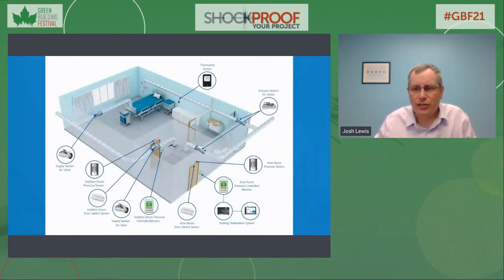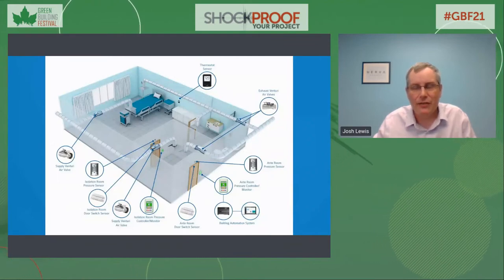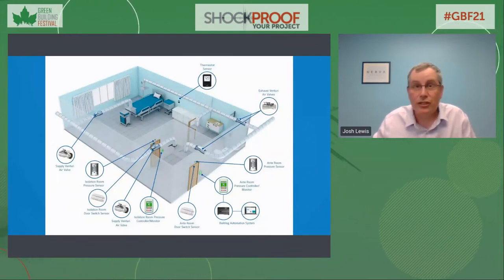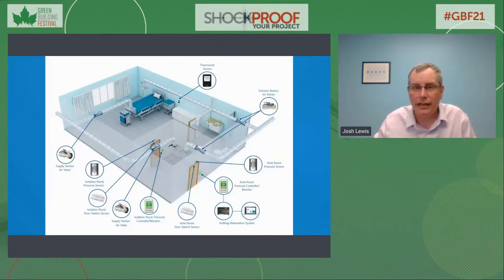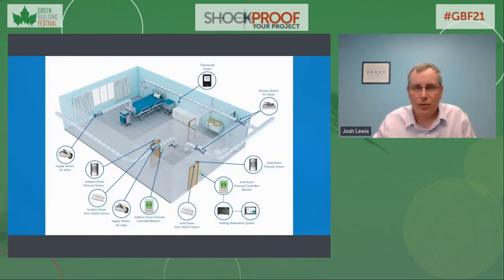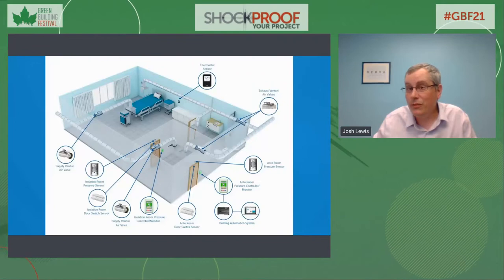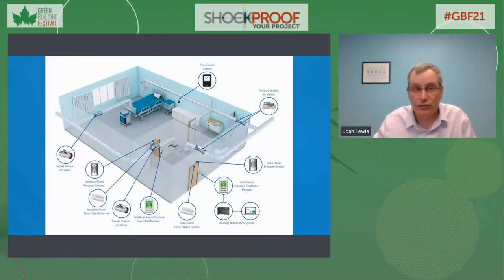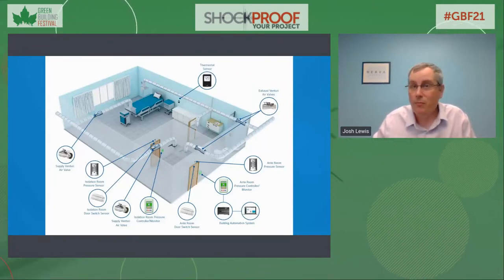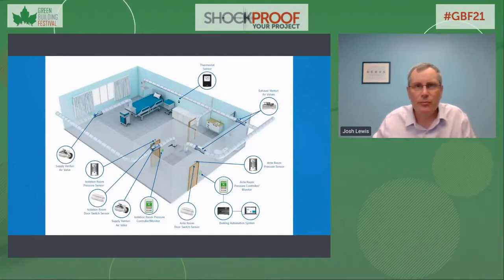There are key considerations that we must reflect upon when looking at the details of how typical energy conservation measures for HVAC systems are likely having a negative impact on indoor air quality. Efficiency, first and foremost, is achieved as a result of tight control of temperature set points in our buildings, both in the occupied and unoccupied or setback states. This measure is not known to have any negative air quality impacts. However, the next four are problem areas.